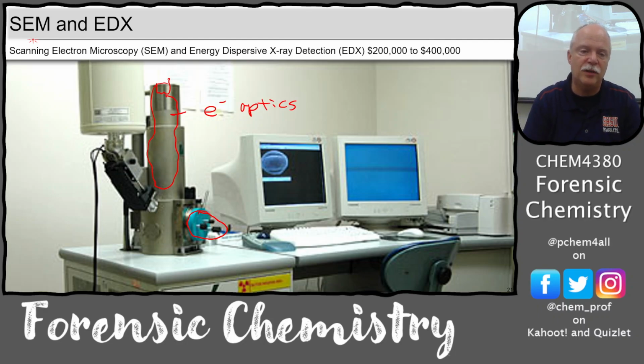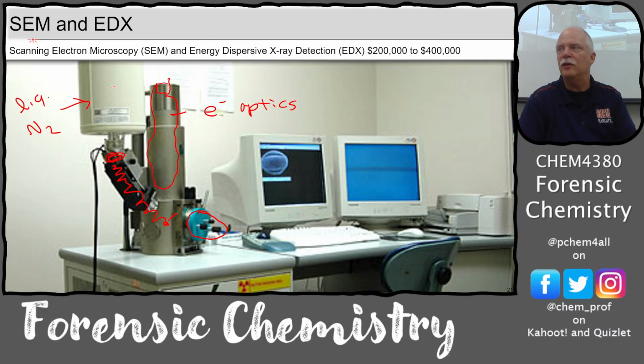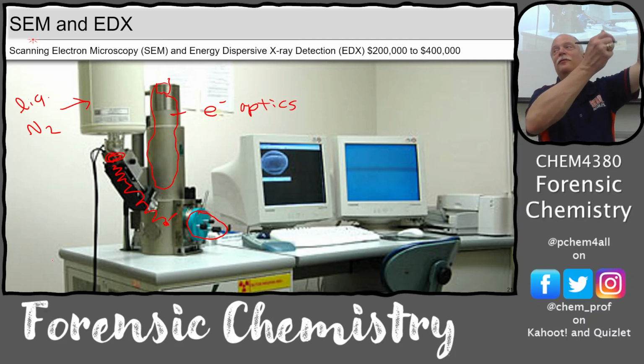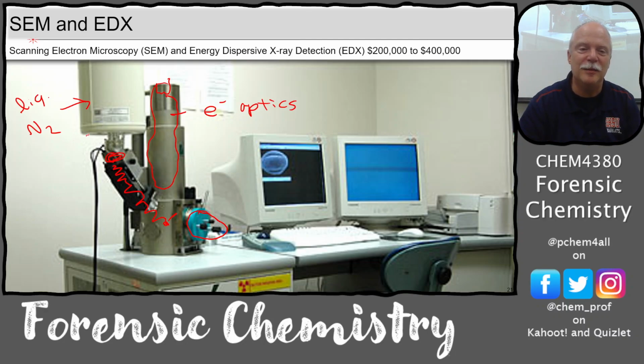And so then it's focused on the sample, and we'll see in a second, the electrons come off the sample and are detected. But it can also emit X-rays, and the X-rays can go up this tube and hit this detector up here, which is liquid nitrogen cooled. So this thing up here is a liquid nitrogen dewar. In our place, we had a little step stool beside us, so you could climb up to refill the liquid nitrogen, but I don't see the step stool. So these X-rays are detected, and let's look to see where those X-rays come from. We'll see that in a second.